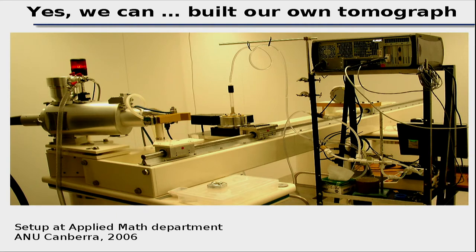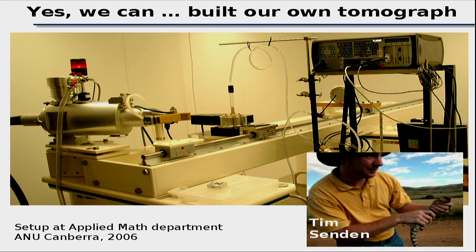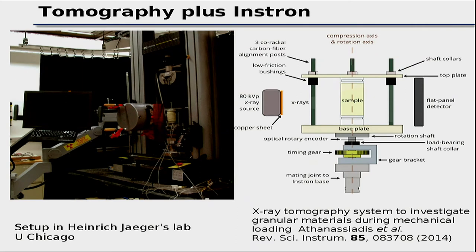Second option: build your own tomography setup. An example from Heinrich Jaeger's lab at the University of Chicago: an extraordinary undergraduate built a complete X-ray setup including an Instron-like compression stage, and published a detailed Review of Scientific Instruments paper covering all the ins and outs. A dental X-ray source (sometimes available second-hand from clinics upgrading their systems) can serve as the X-ray tube; a scintillator screen with a normal CCD camera replaces an expensive flat-panel detector; a rotation stage starts at around $1,000. Total cost can be brought into the ~€50k range.